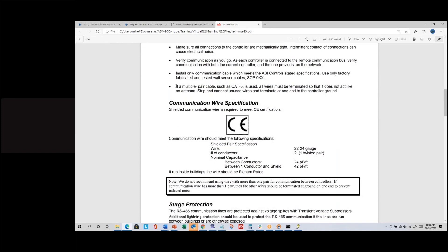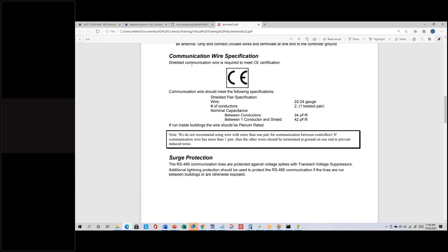There's also a mention about not using multiple pairs of cables. Sometimes people like to run two pairs in case one fails, so they have a backup without running new wire — that makes some sense. But if you do that, the unused pair needs to be grounded as if it were the shield wire, meaning terminate one side and land it to ground. Otherwise an unused pair can act like an antenna with no path to ground.